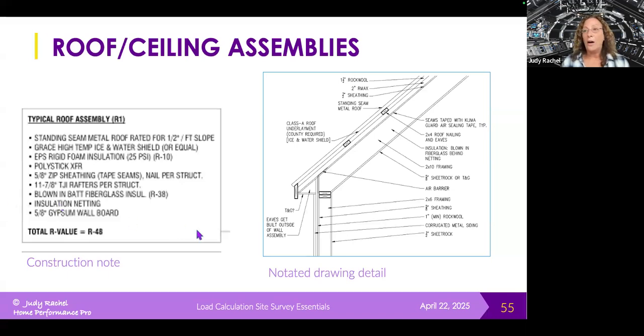Sometimes I luck out and get a box like this that just lays it out for me. I've got a standing seam metal roof, and ice and shield underneath that, which is actually difficult to model. You have a choice, since there are certain pieces of the assembly you don't necessarily have to put into the load calculation, because some of it is too hard to find out the density, conductivity, or R value of the material. But we need to know what that outside surface is, whether it's metal seam, asphalt shingle, or clay tile.